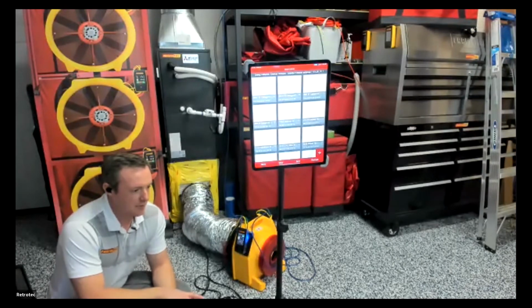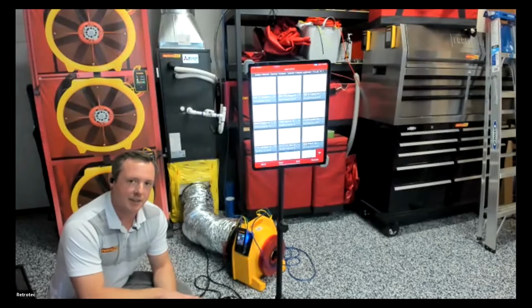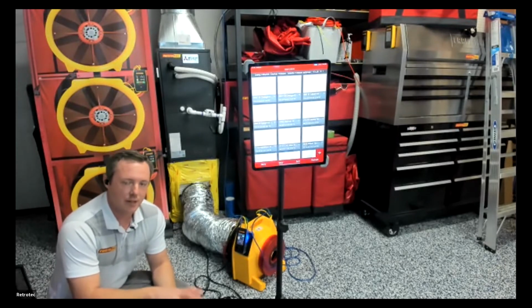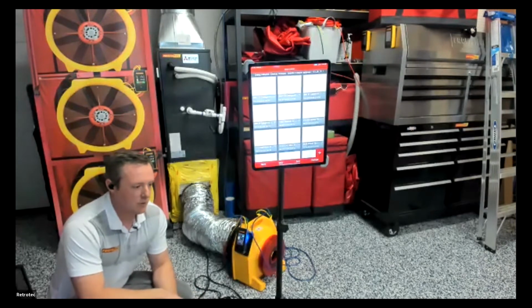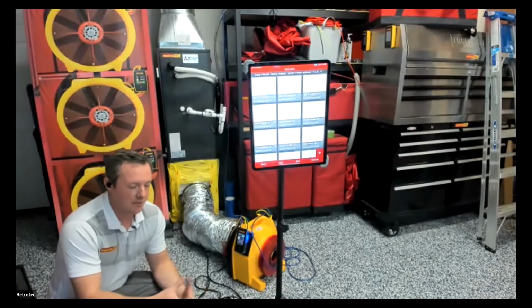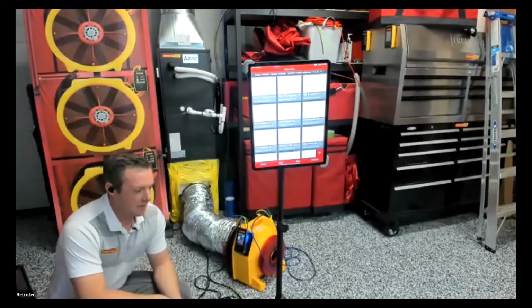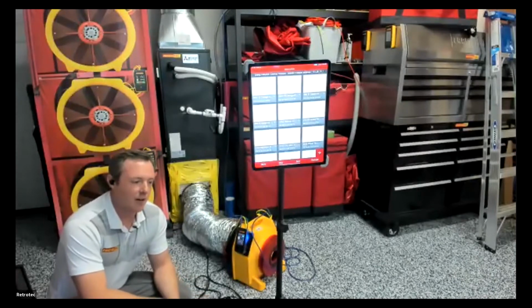But yeah, it's important to look up what your test standard requires. If you're testing to ResNet, they have some different requirements that they tell you to do. A lot of times, they'll tell you to kind of leave it in its natural state. Power dampers are always going to be closed if they're not running. And you want to look at and see how often that ventilation is running to determine that.